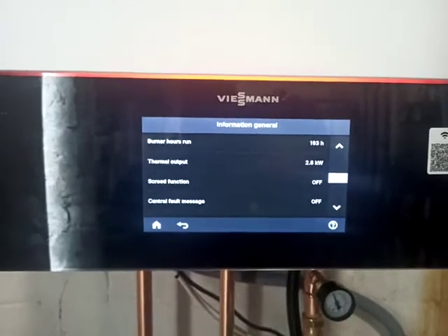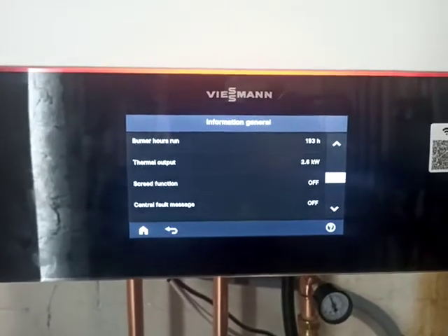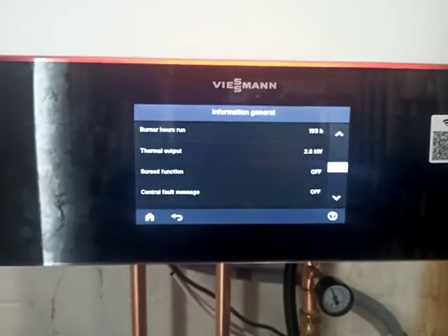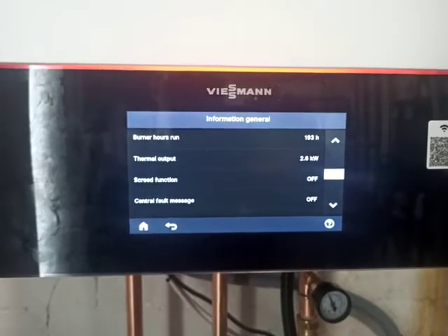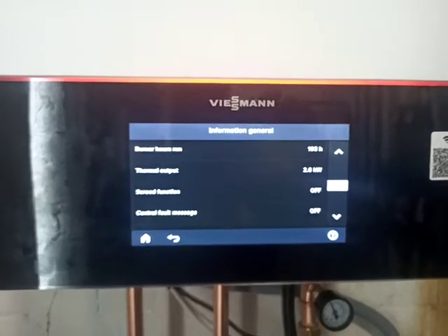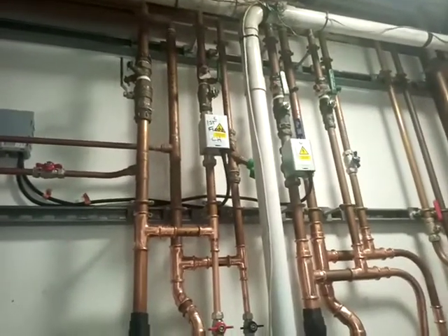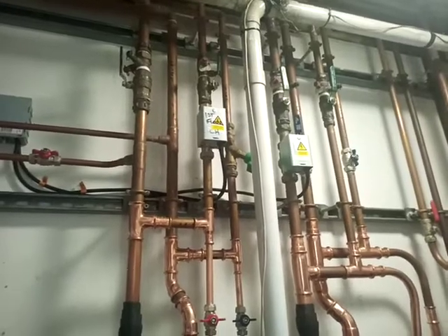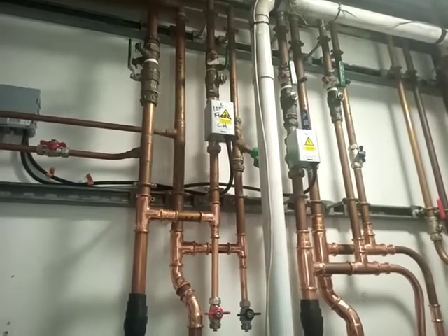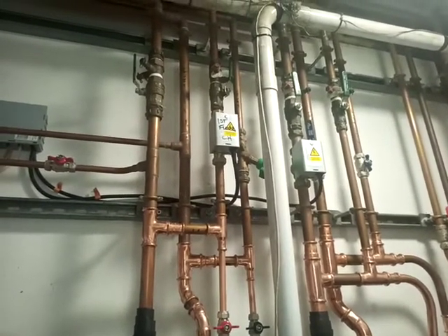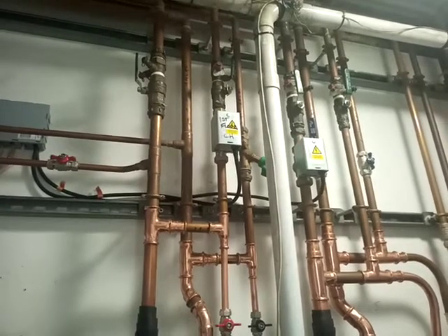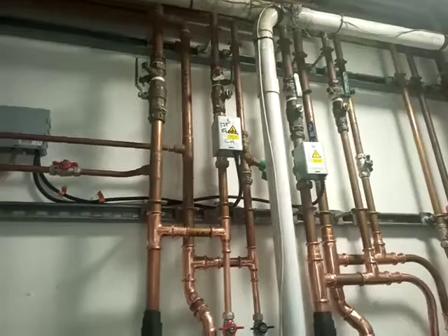Now that would suggest that we could do the same job at -1 at around about 12 kilowatts, but it's not quite as it seems, because we put a couple of zone valves in on room stats. There's actually two quite big chunks of the house that are turned off at the moment, because they don't require the extra heat in there, and we didn't want to achieve the lower temperatures with Divicons, so a little bit confusing.